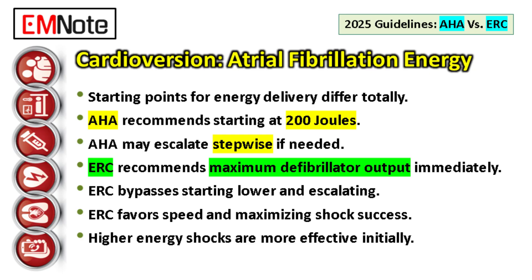The ERC, however, recommends an initial synchronized shock at the maximum defibrillator output — right away, completely bypassing a lower starting point. It favors speed and first-shock success. If you practice under ERC guidelines, you must check your specific device's maximum output — could be 360 joules or something else depending on the model — and select that right off the bat, eliminating the potential delay of starting low, failing, going higher, and failing again.